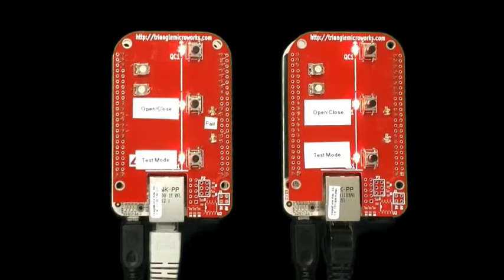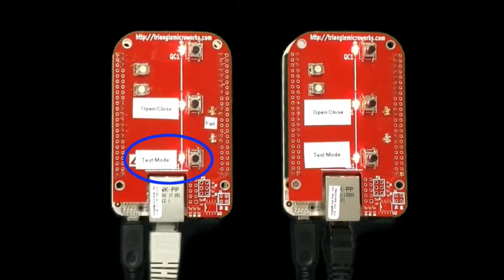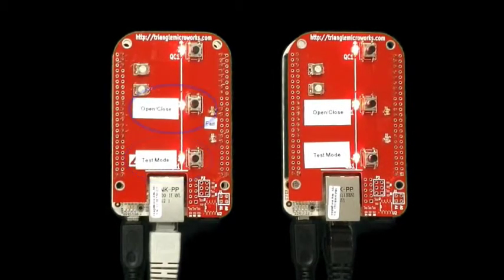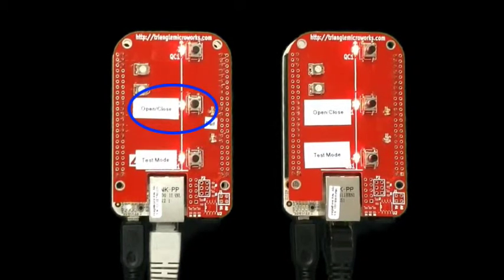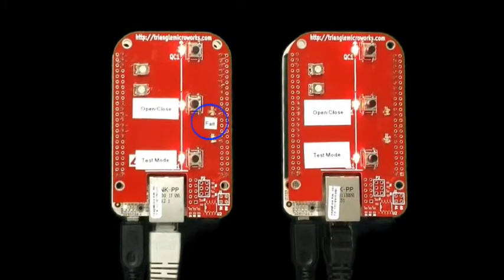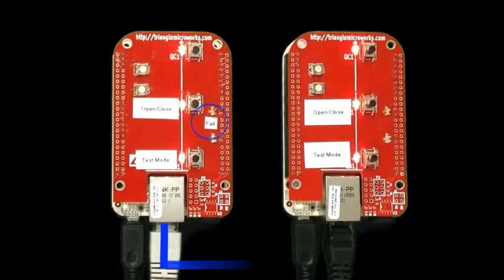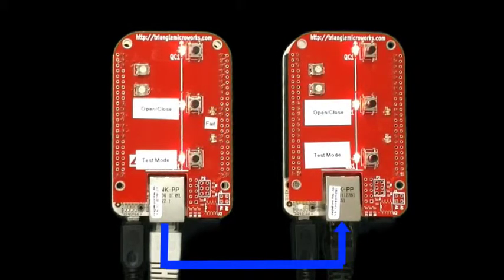On one board, the lower switch puts the breaker into failed test mode. A second switch signals the board that an overcurrent condition has occurred. The board responds by simulating a breaker failure and sending GOOSE messages.